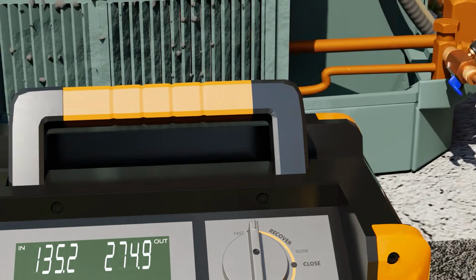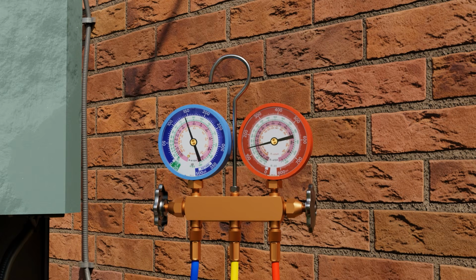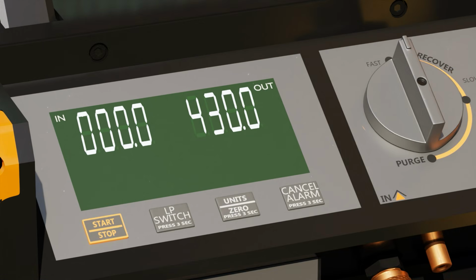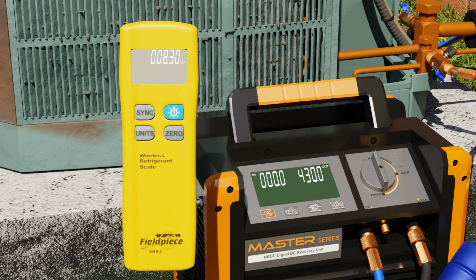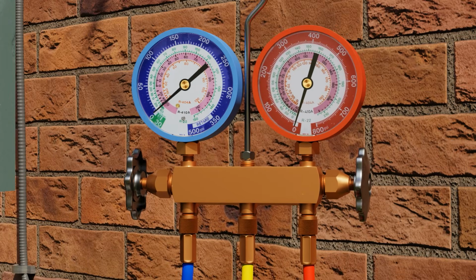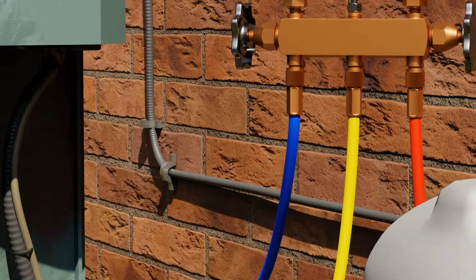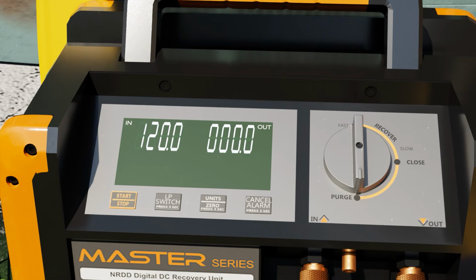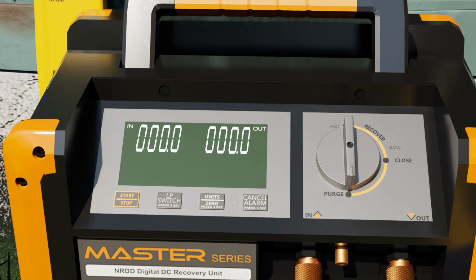Wait until you recover to 0 psi or slightly below 0 psi. Make sure you don't overfill your tank by monitoring the weight of the refrigerant going into the tank. Next, you purge your machine and shut off the tank. Not all machines have a purge option, but this NAVAC NRDD machine does.